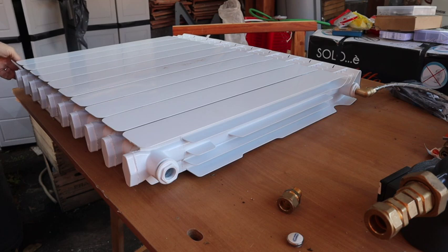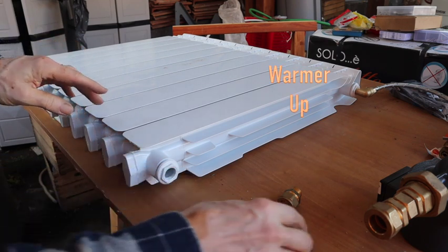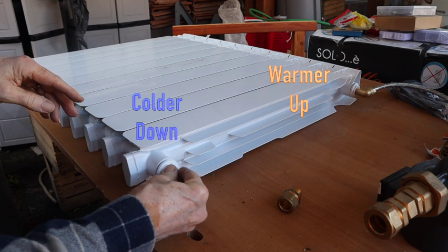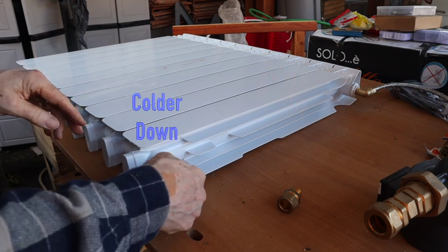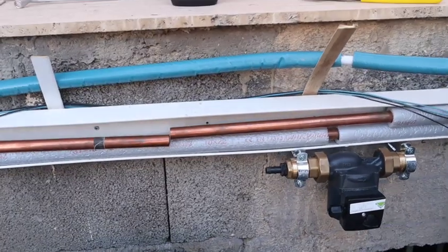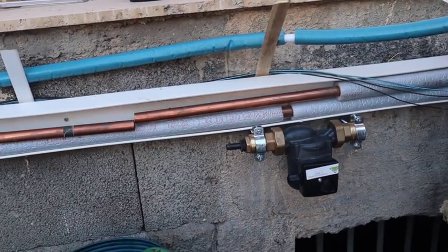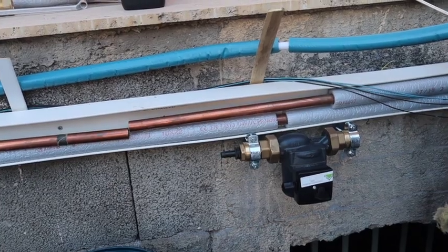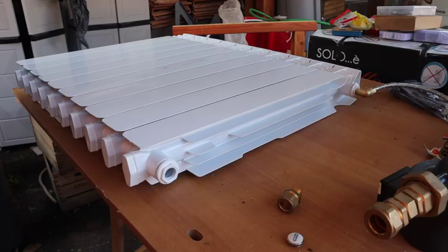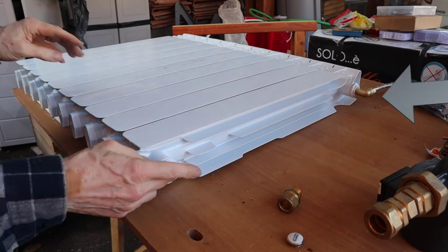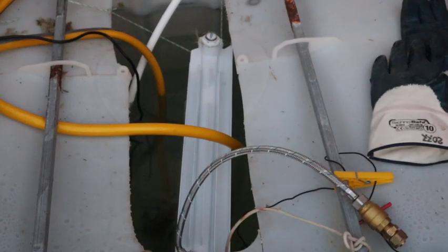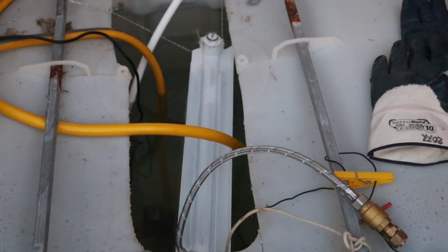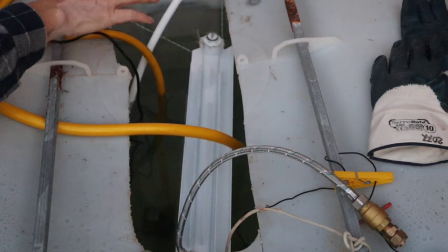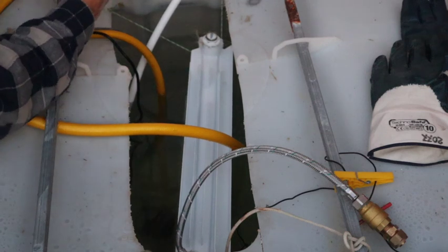The radiator inside the warm tank will be with its upper side in the warmer water layers and cooler at its lower side because of the stratification. So, connect the return pipe of the central heating, which is the cooler of the two connections in the winter, to the lower connection of the radiator and let the water leave the radiator where the water in the tank is warmer, at the surface. In this way, the temperature profile in the radiator has the same direction as that in a stratified tank. That's better for efficiency. We will see this argument next spring because we are now in our winter house.